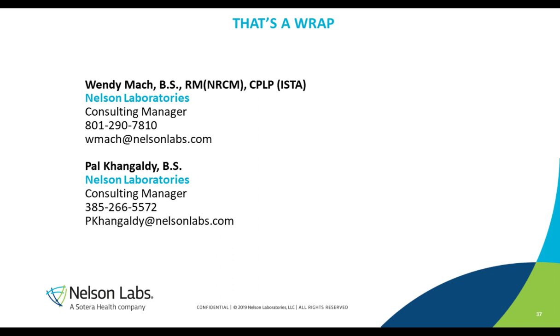Okay, fantastic. Next question. If the product is sold in market as non-sterile and the manufacturer is getting the product as a finished good from a supplier, does the product packaging need a validation? So it needs the minimum testing that I mentioned, where you're verifying the integrity and the cleanliness. I would also probably look at the shipping too. The last thing you want to do is make this product and then send it to your client and it gets there in a non-usable state. This is one of those things where market is driving the testing, not the standards. The MDR was specific about ensuring that even if it's non-sterile, those two items do need to be addressed. And I think when it comes to the FDA, that's where they're saying market type issues drive the test.